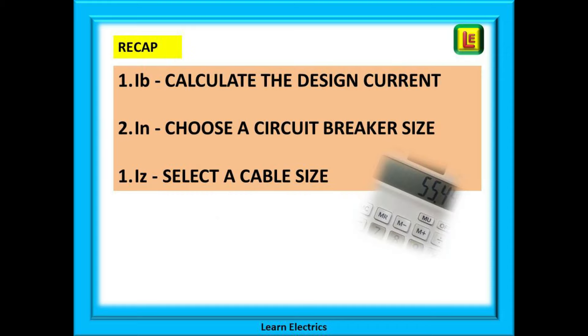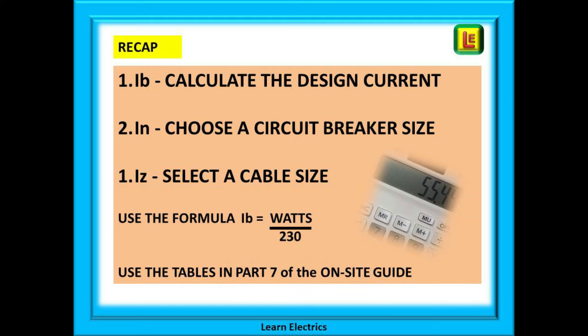So a recap: first, calculate IB the design current; second, decide on the size of breaker for IN; and finally, select a cable size to give us IZ. Learn to use this very easy formula: IB equals watts divided by 230. All the other information you need will be in part 7 of the on-site guide.